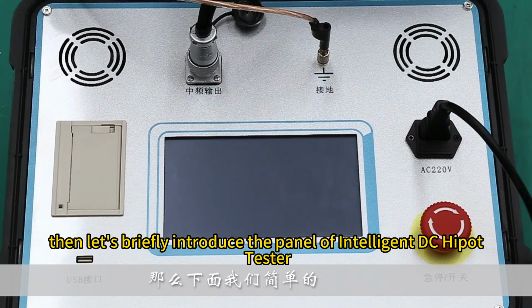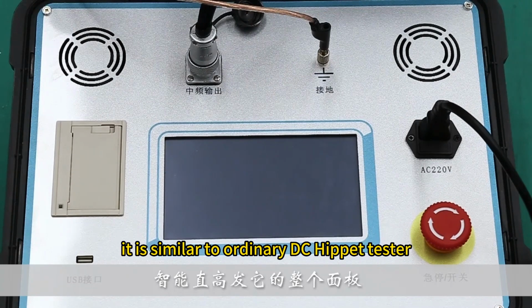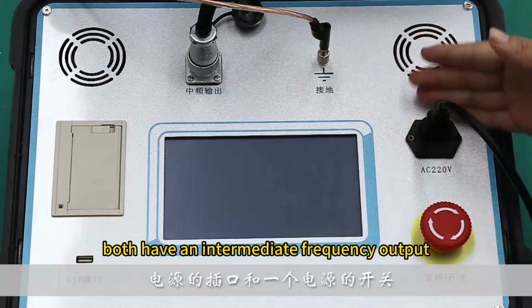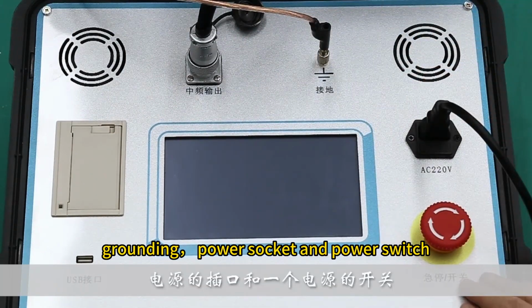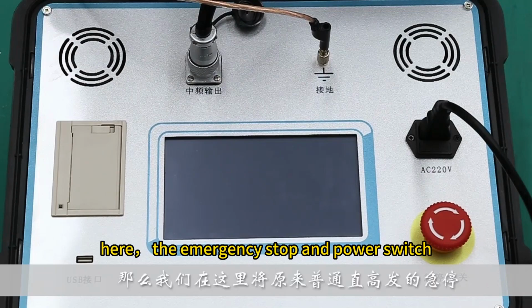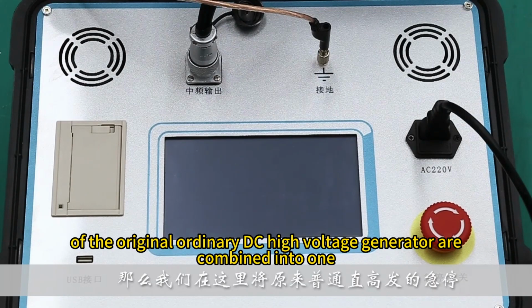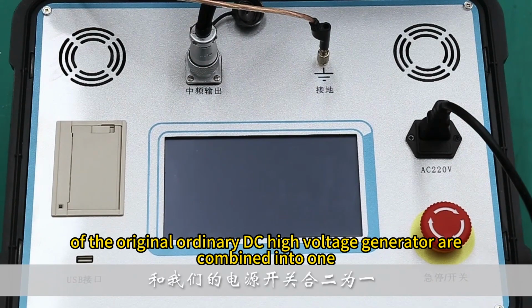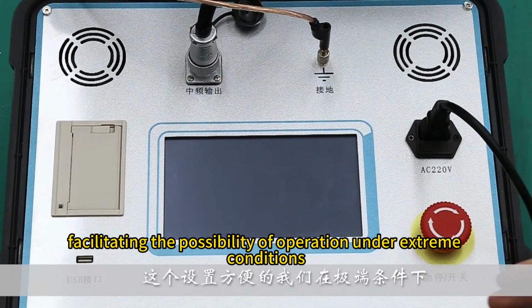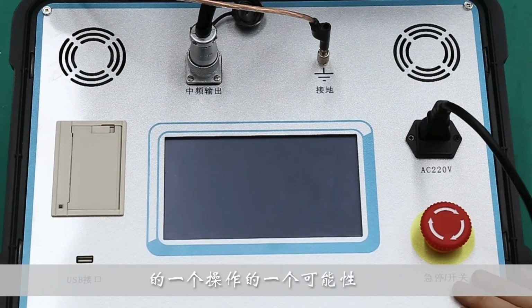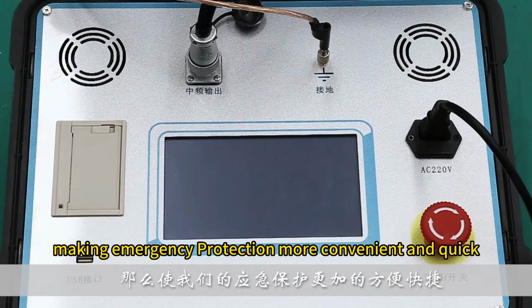Then let's briefly introduce the panel of the intelligent DC Hipot tester. It is similar to the ordinary DC Hipot tester. Both have an intermediate frequency output, grounding, power socket and power switch. Here, the emergency stop and power switch of the original ordinary DC high-voltage generator are combined into one, facilitating operation under extreme conditions, making emergency protection more convenient and quick.